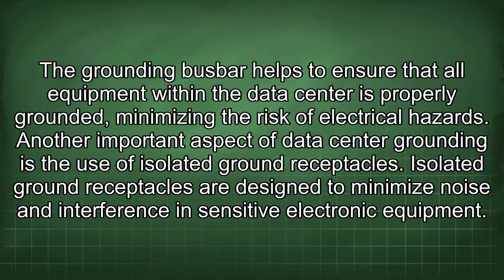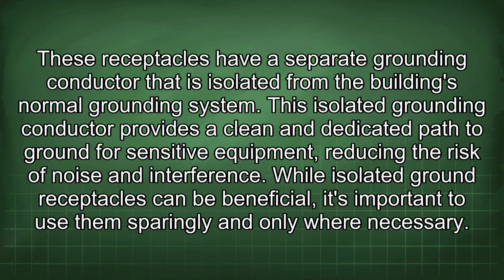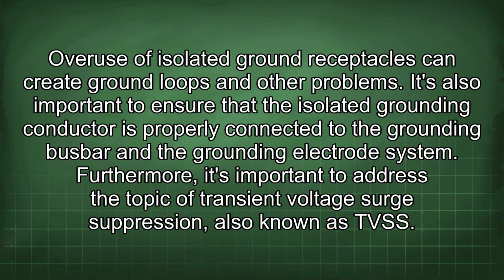Another important aspect of data center grounding is the use of isolated ground receptacles. Isolated ground receptacles are designed to minimize noise and interference in sensitive electronic equipment. These receptacles have a separate grounding conductor that is isolated from the building's normal grounding system. This isolated grounding conductor provides a clean and dedicated path to ground for sensitive equipment, reducing the risk of noise and interference. While isolated ground receptacles can be beneficial, it's important to use them sparingly and only where necessary. Overuse of isolated ground receptacles can create ground loops and other problems. It's also important to ensure that the isolated grounding conductor is properly connected to the grounding busbar and the grounding electrode system.